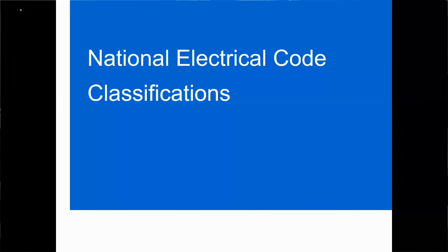Now, when you say testing the equipment to mean that it's still going to operate properly, I'm going to try and answer the question the way I think it means, but I could possibly be assuming the wrong intent of the question. When the equipment is originally tested by UL, it's designed to contain the explosion, which we'll talk about a little further in the presentation. When that equipment is tested, it's tested that it'll operate continuously and perform its function, providing that any maintenance and installation has been done correctly. When it is out in the field, you shouldn't need to do additional testing for the equipment. Okay. Now, if that wasn't exactly the way the question was intended, as we proceed forward, questioner, please feel free to chat again and allow further detail, and we'll do the best we can to answer that.